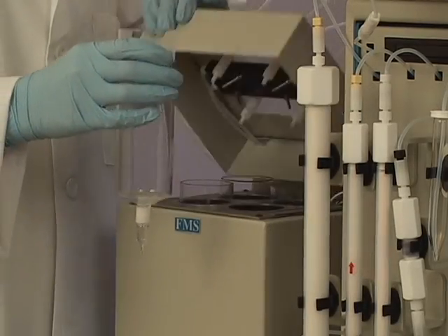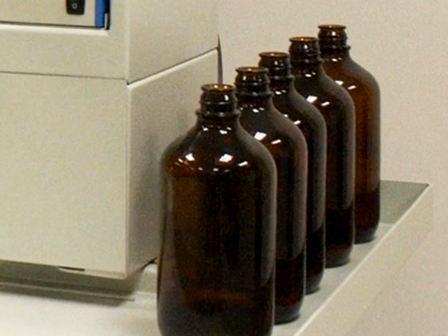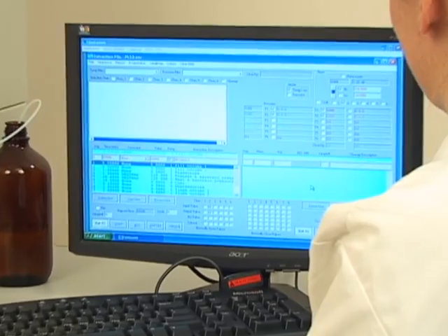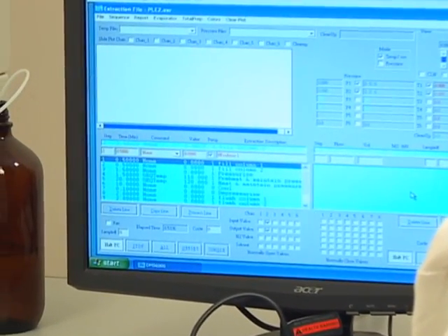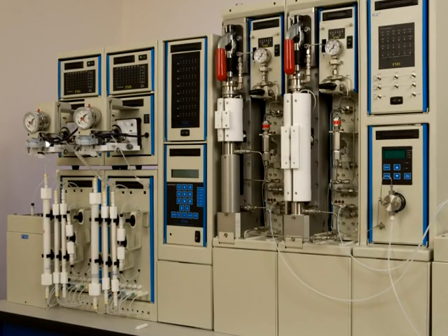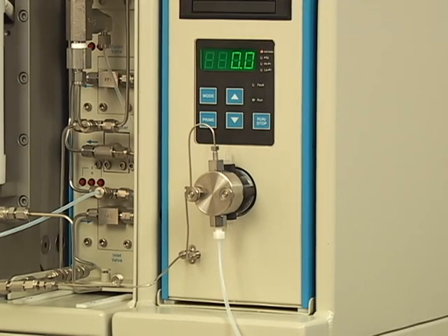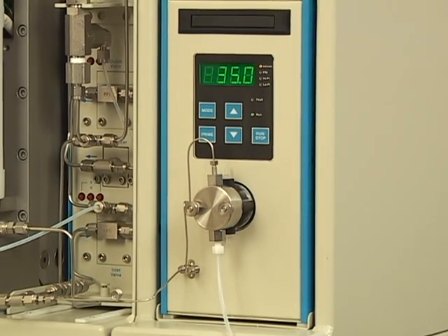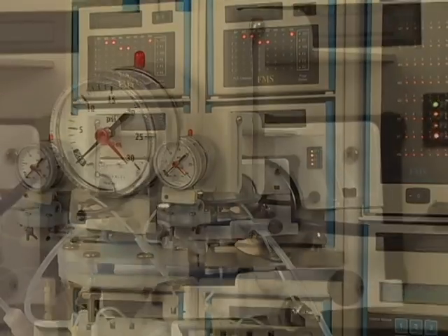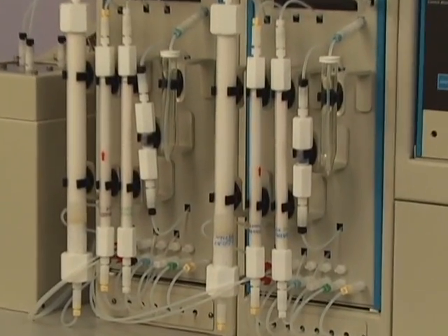Clean, empty, 200-milliliter glass tubes are placed into the evaporator. Prepared solvents are placed in the appropriate bottles for cleanup and extraction. The total rapid prep program is then opened, along with temperature and pressure log files, for extraction and sample cleanup. The program is launched. Two cycles of extractions may be needed for full recoveries. Extraction of fish begins simultaneously with the conditioning of cleanup columns and the preheating of evaporators.